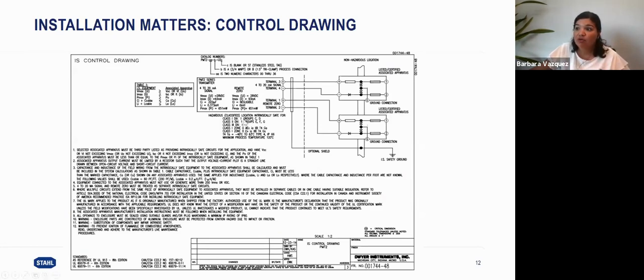So here, I don't know if you are able to see this little font clearly. It says that this device can be installed in hazardous areas, intrinsically safe for Class I Div.1 Group C and D. So remember we talked about knowing the group of gases?